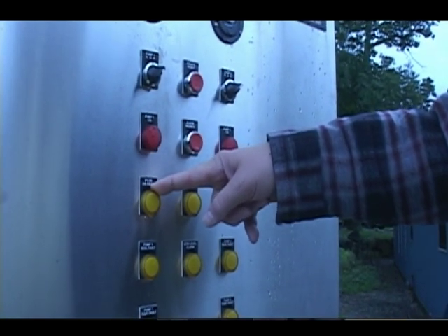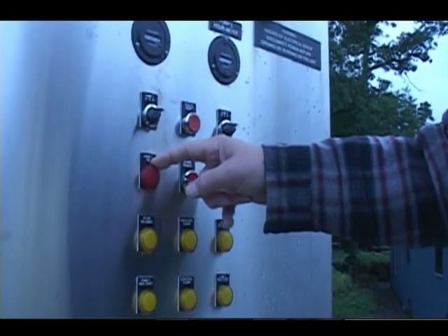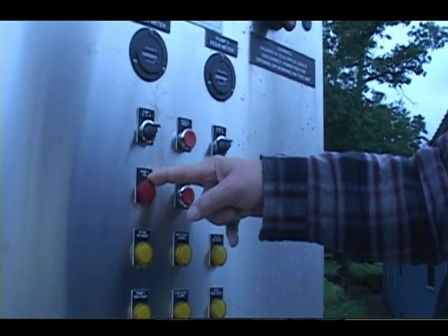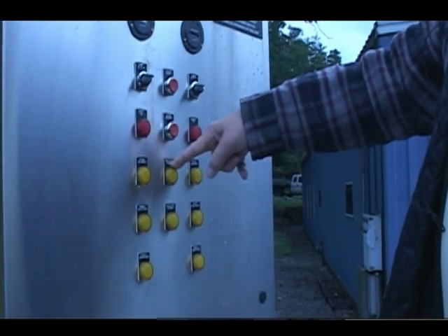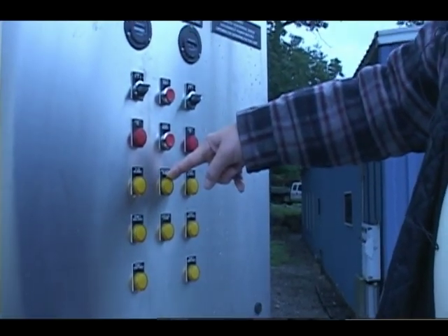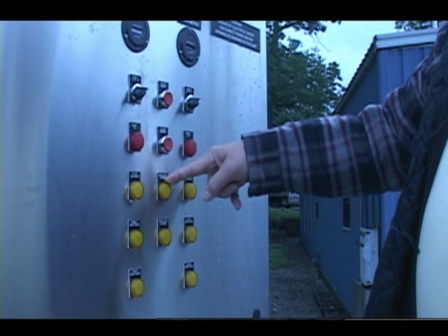I'll show you more details on that in a minute. The pump on indicating light just says that the pump is on. Right? So we have a high level alarm. That means for some reason a high level float has been made. It should not be made unless there's a fault or for some reason the pumps are not pumping as much as what they should be.